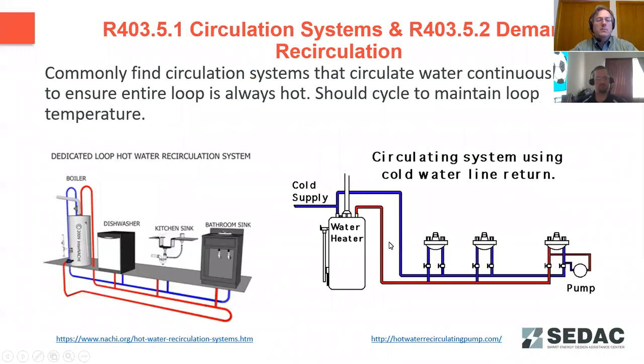Some examples of what those different systems look like. On the left is the dedicated hot loop recirculation system. And on the right is your demand recirculation system, where you've got a pump out in the system. Usually it's at the farthest leg of your hot water supply line. And anytime one of those faucets kicks on, or a sensor detects that someone is using hot water, that pump kicks on to recirculate.